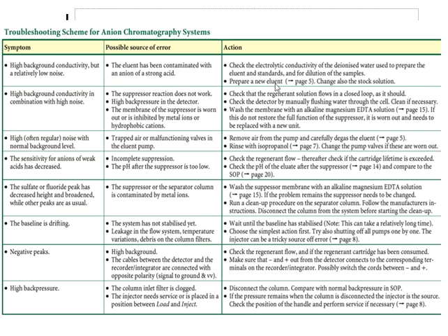So you just want to check the conductivity of the water. And if you think that it is pure DI water, then a lot of times to fix this, just dump the mobile phase out and make it new again and try it one more time. If someone did contaminate it, which is the most common cause of the problem, then a good rinse of the bottle completely out, and making sure that you wear gloves so that any kind of salty, sweaty residue that might be on your hands is not contaminating the mobile phases.